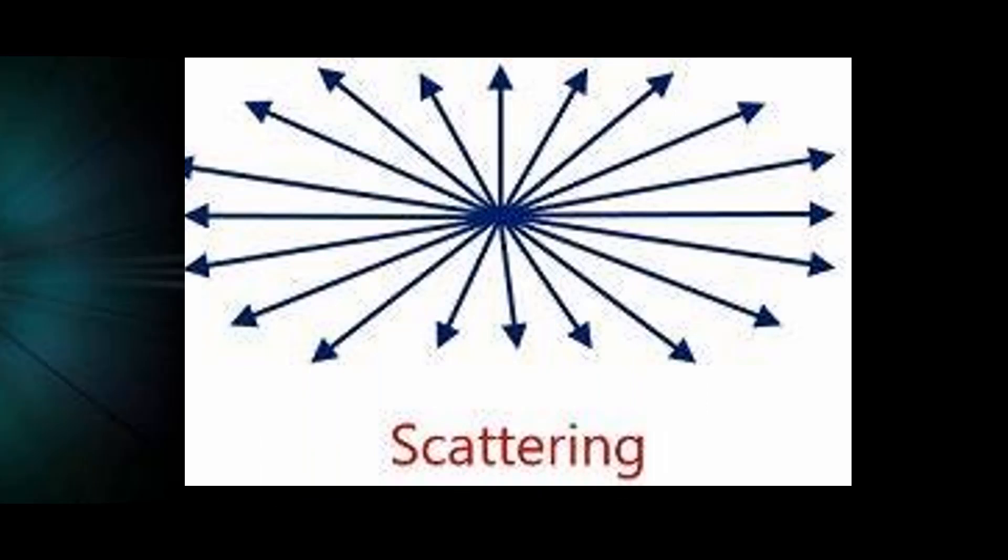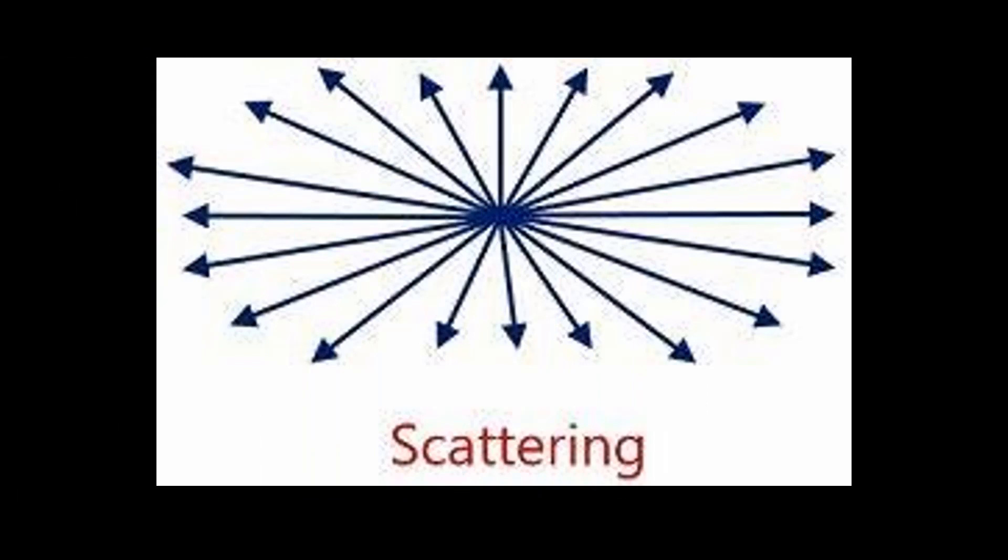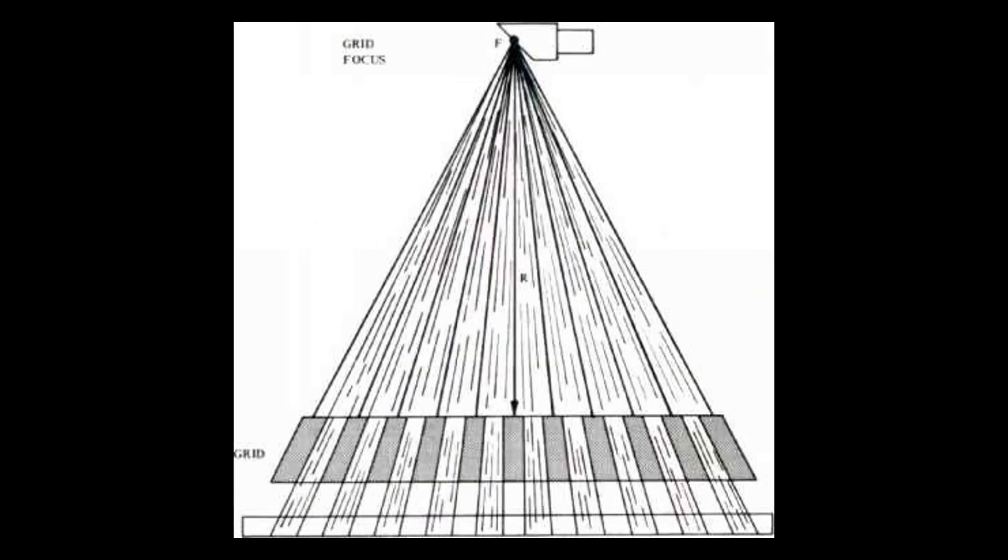Well, in the same way, x-rays are focused in the middle, and they diverge out at different angles the further you get from the centering point. So now you can understand the design of grids. The lead strips on the grid are aligned straight ahead in the center. And as the strips get further out, they begin to angle along the direction that the photons are traveling in.